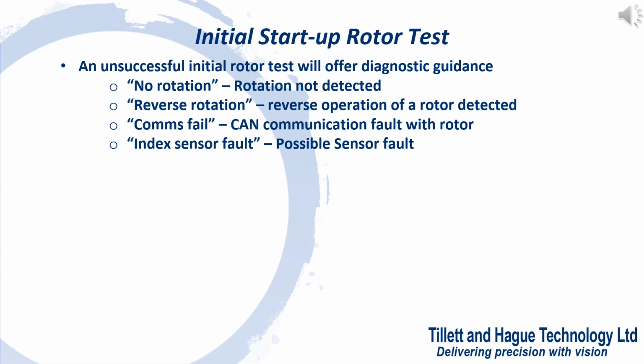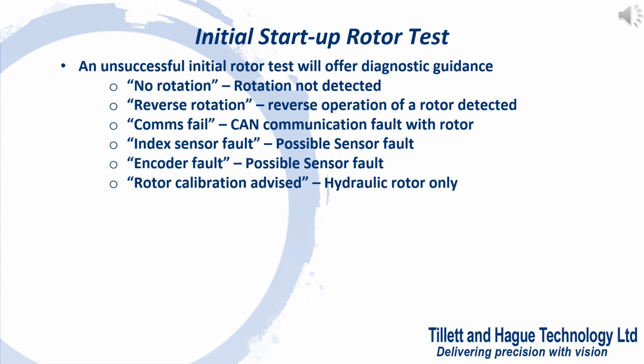An index sensor fault suggests a sensor that should be triggered once per revolution is not being triggered as expected. Run a rotor test and view the output graph to help with diagnosis. An encoder fault suggests the rotor speed sensor is not giving the expected smooth output, and a fault has been detected. Run a rotor test and view the output graph to help with diagnosis. Rotor calibration advised. This message should only be displayed with hydraulic rotors.